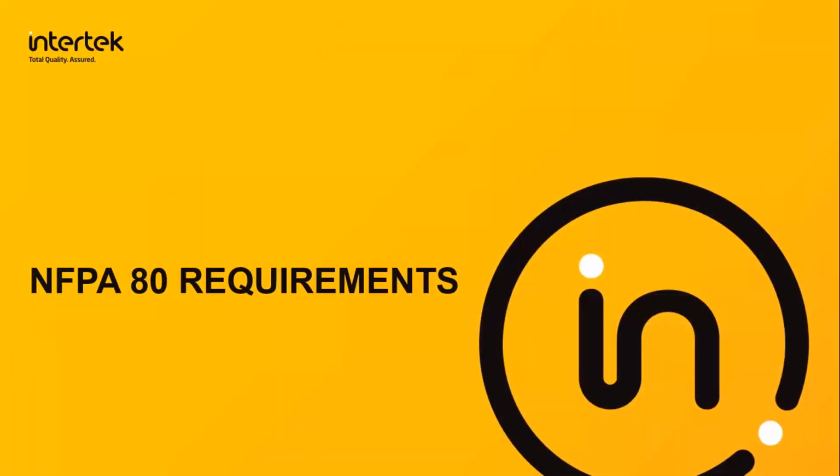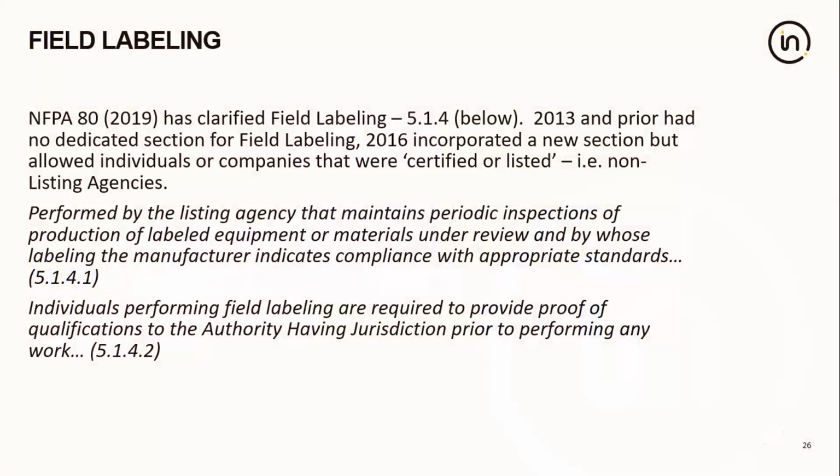From there, we're going to segue into NFPA 80 requirements. For those of you not familiar with NFPA 80, it's the standard for fire doors and other opening protectives. It's a great document, great tool, goes into detail on ongoing maintenance requirements, inspection requirements, installation, labeling, all sorts of great information.